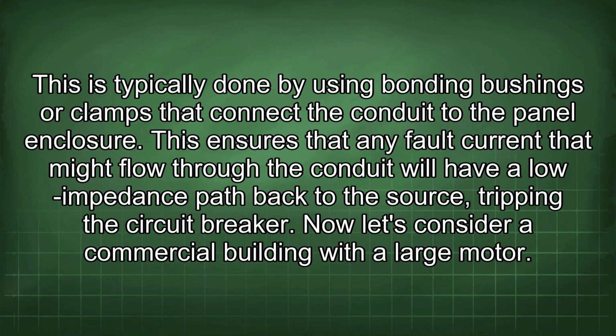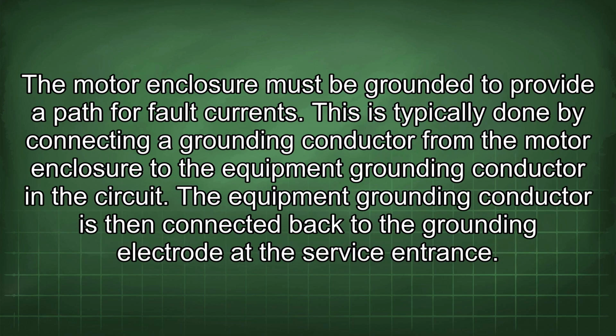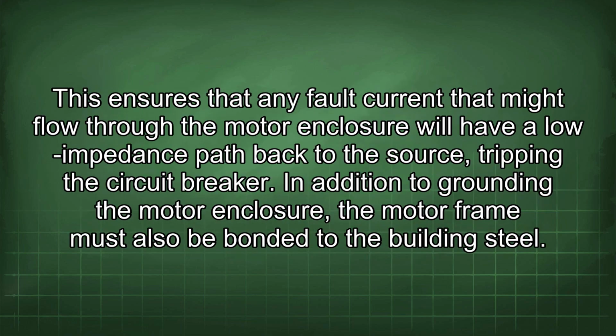Now let's consider a commercial building with a large motor. The motor enclosure must be grounded to provide a path for fault currents. This is typically done by connecting a grounding conductor from the motor enclosure to the equipment grounding conductor in the circuit. The equipment grounding conductor is then connected back to the grounding electrode at the service entrance. This ensures that any fault current that might flow through the motor enclosure will have a low impedance path back to the source, tripping the circuit breaker.